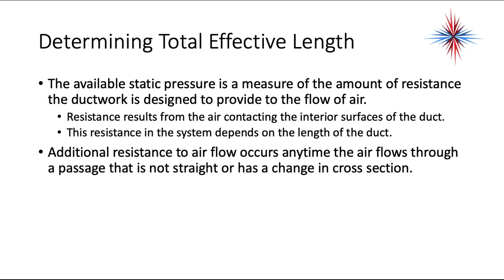The available static pressure is a measure of the resistance the ductwork is designed to provide to airflow. Resistance results from air contacting the interior surfaces of the duct, and depends on the length and type of duct. Additional resistance to airflow occurs whenever air flows through a passage that is not straight or has a change in cross section — for example, through a 90-degree elbow, a reducer, or even a 45-degree elbow. Every fitting will have a pressure loss.